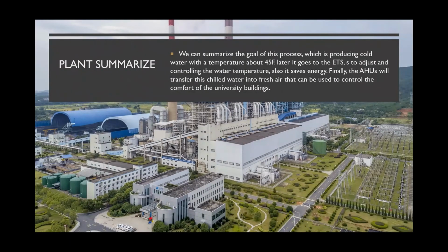Finally, I can summarize the goal of this process or this plant, which is producing cold water with a temperature of about 45 Fahrenheit. Later, it goes to the ETS to adjust and control the water temperature. Also, it saves energy. Finally, the AHU will transfer this chilled water into fresh air that can be used to control the comfort of the university's buildings.